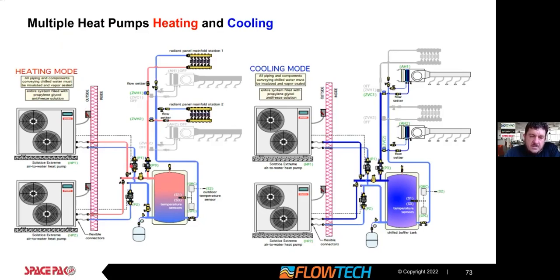Oftentimes I get questions, hey, can I just keep that circulator on, through a zone control or not wire it to the unit? And we don't like to see that. So 2-unit applications. We've got other piping diagrams too, reverse return for larger commercial stuff. If you have a commercial application, if you're in my territory, reach out to us and we'll get on with the pre-sales from SpacePak to go over your particular application.